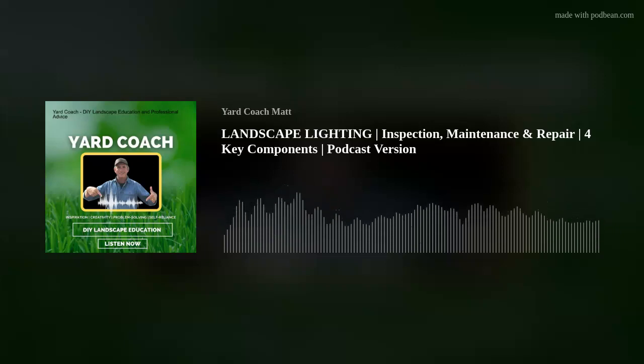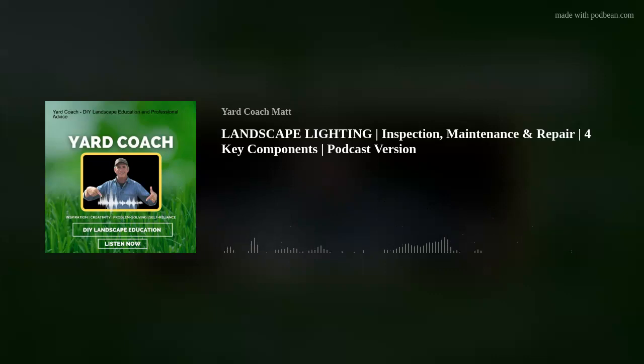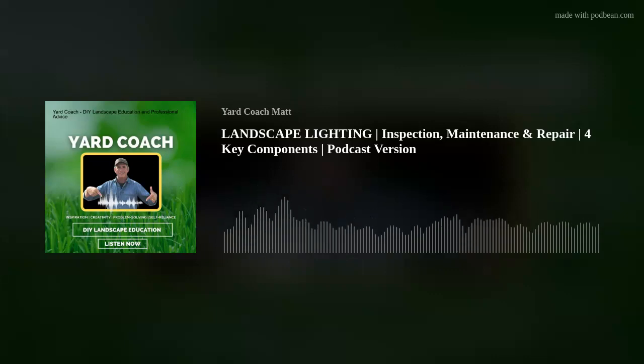All right, once you have your transformer all dialed back in, cleaned up, and ready to go for the next 3 to 6 months, whatever, we move on to the cabling itself. And we're going to start back at that transformer. We've already inspected the cabling inside the box. Well, now let's check it as it leaves. Make sure there's no nicks, cuts, anything as it leaves that sharp.